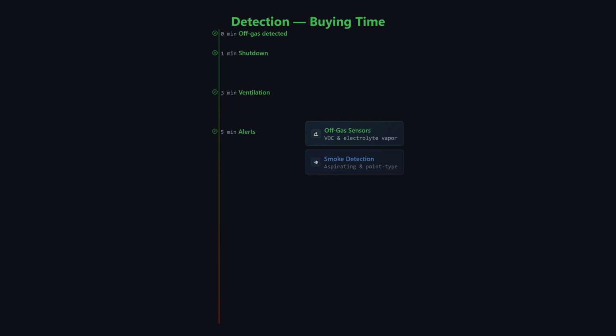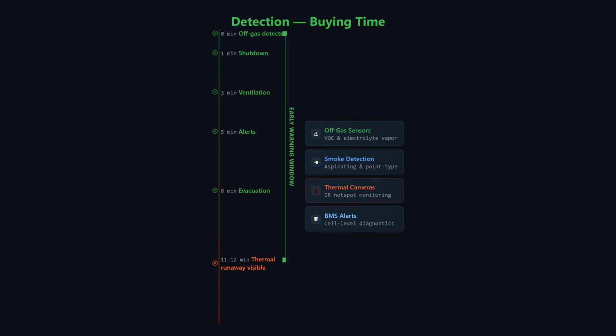The most critical safety measure for BESS isn't suppression, it's detection. Off gas sensors can detect battery venting gases 11 to 12 minutes before thermal runaway becomes visible. That's 11 minutes to shut down the system, activate ventilation, alert emergency services, and begin evacuation. Multi-layer detection combines off-gas sensing with smoke detection, thermal monitoring, and battery management system alerts. The key is speed. Every minute of early warning reduces the risk of gas accumulation reaching explosive concentrations.